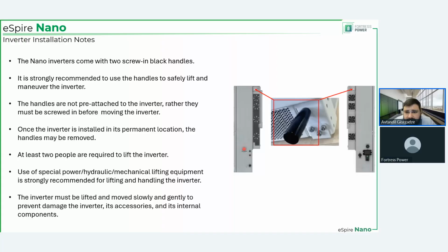So, inverter installation notes. These handles I mentioned before when we were talking about the inverter packing list. These are screw-in handles. They go on the sides right here, and you just screw them in. Hand tight is fine. These make it easier for you to maneuver the inverter in the field and raise it and so forth. You can use these handles with a crane with straps. That's also totally fine. You can also remove them once you're done installing the inverter.